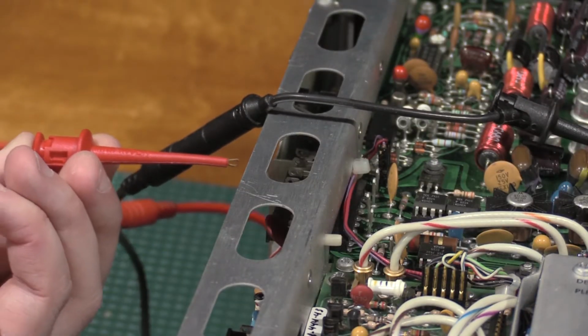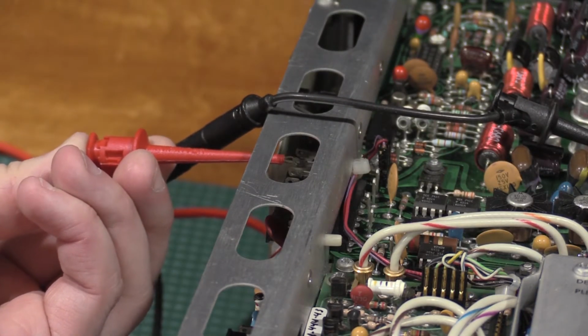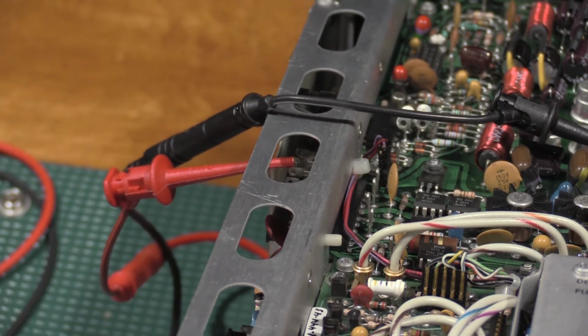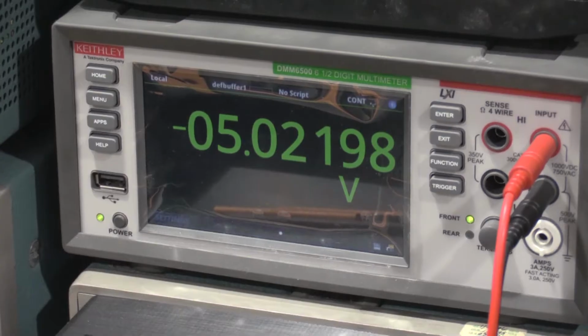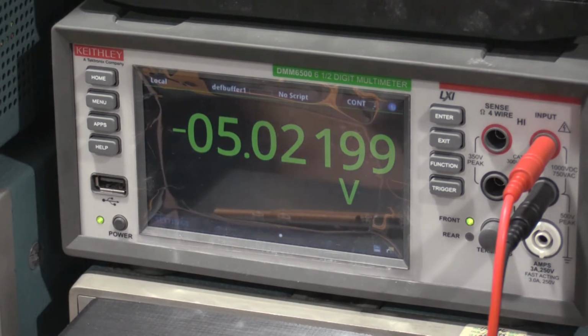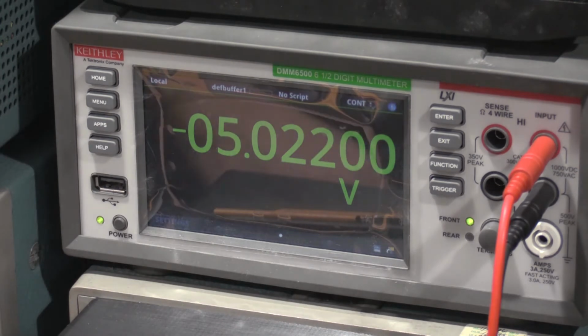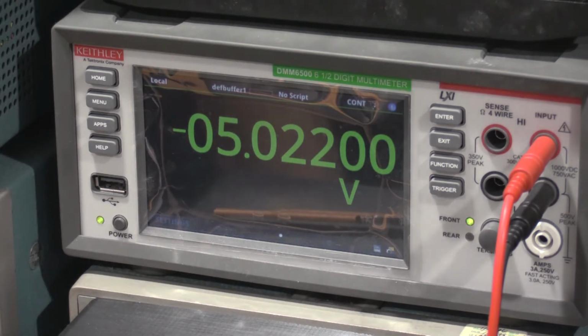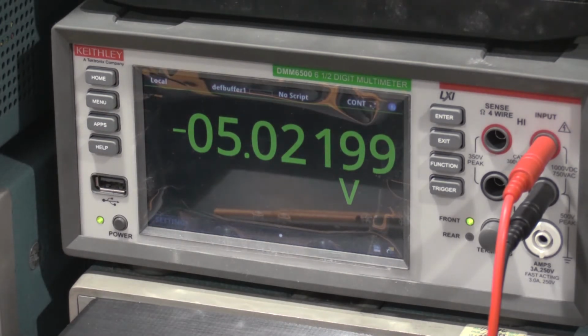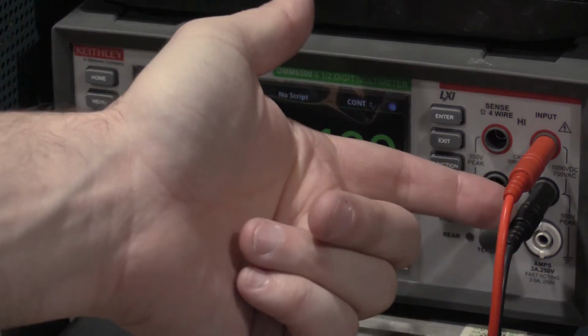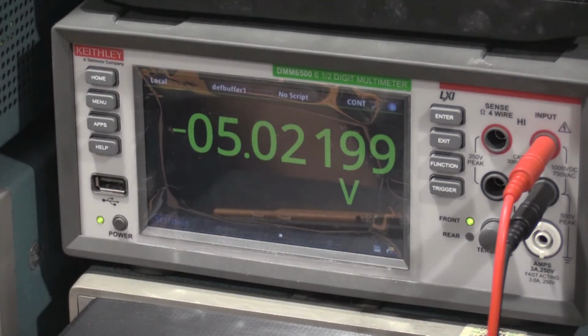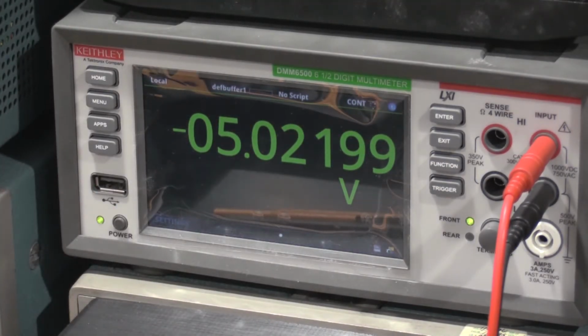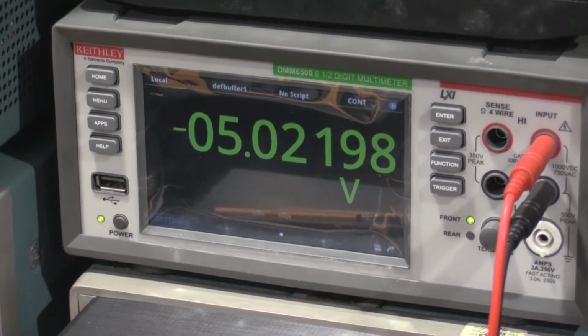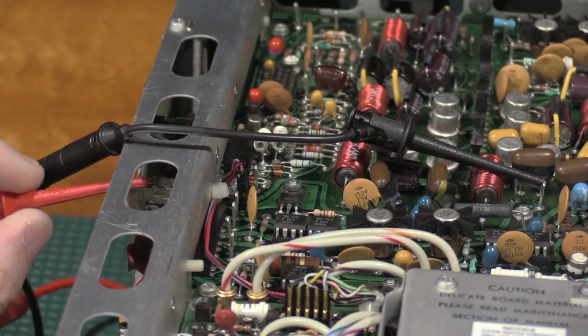Minus 5 is right here. Looks good. Tolerance is 100 millivolts, so we're at, yeah, it's perfect. It should also be noted that all of this is ground reference to the ground point on the power supply board. So the low side has not needed to move for any of these. Next one's negative 15, tolerance of 300 millivolts. Negative 15 is one back.